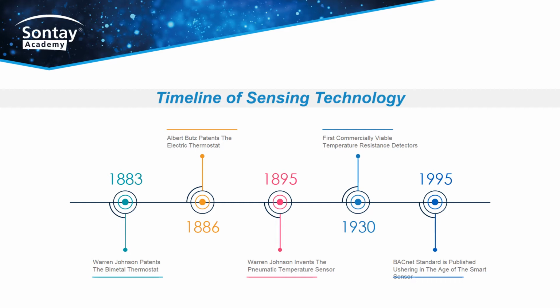However, the sensing devices remained relatively unchanged, with DDC controllers requiring sensors for input in order to perform control algorithms. Although not the first open protocol, the publication of the BACnet standard in 1995 provides us with a marker for the advent of the smart sensor. Unlike their predecessors, smart sensors are able to communicate multiple values on a single network bus, reducing physical input or output requirements on DDC controllers, and increasing the flexibility of the sensing devices themselves.